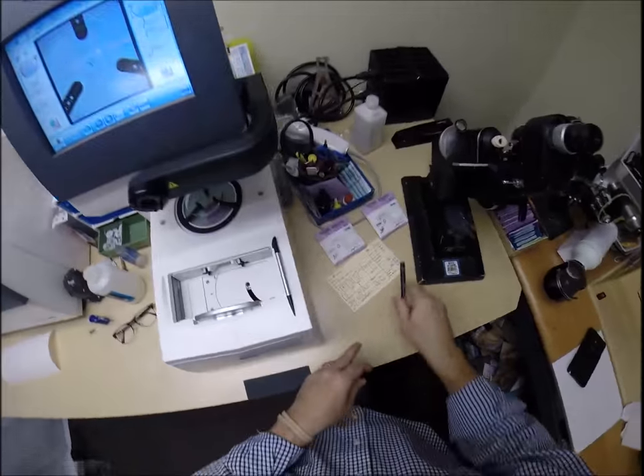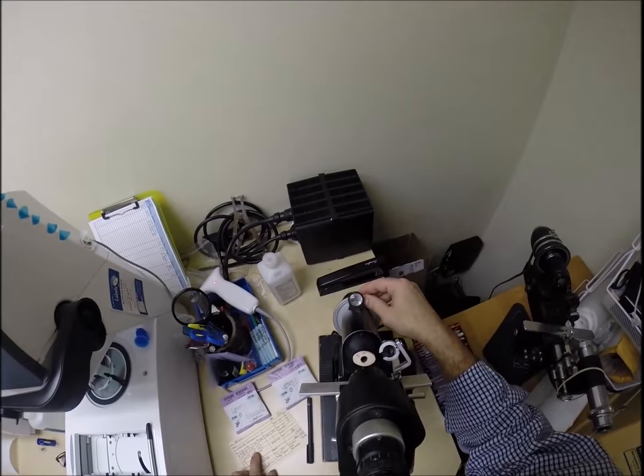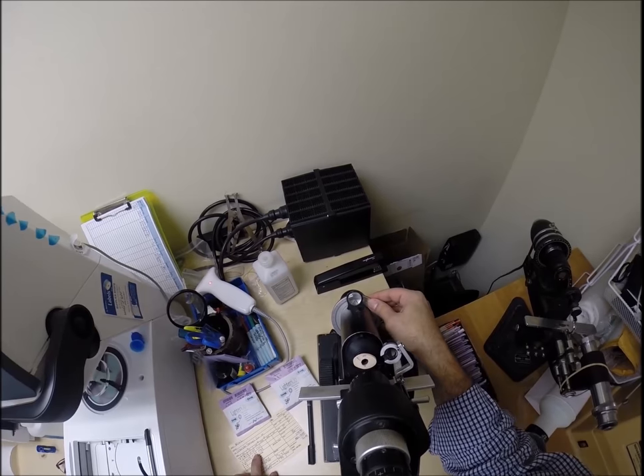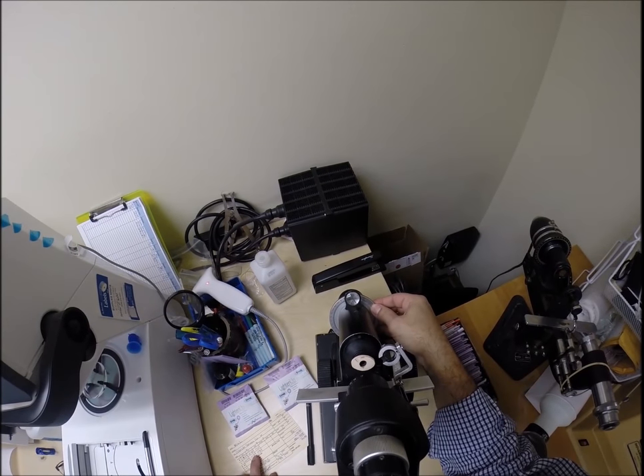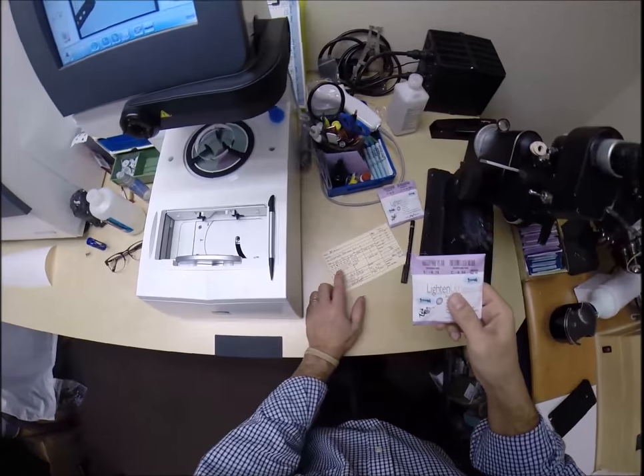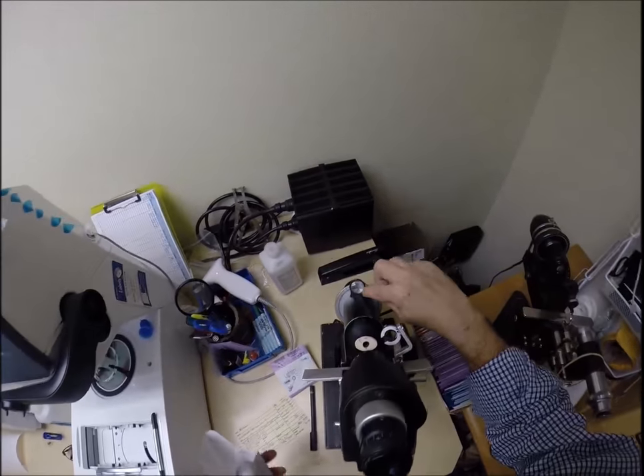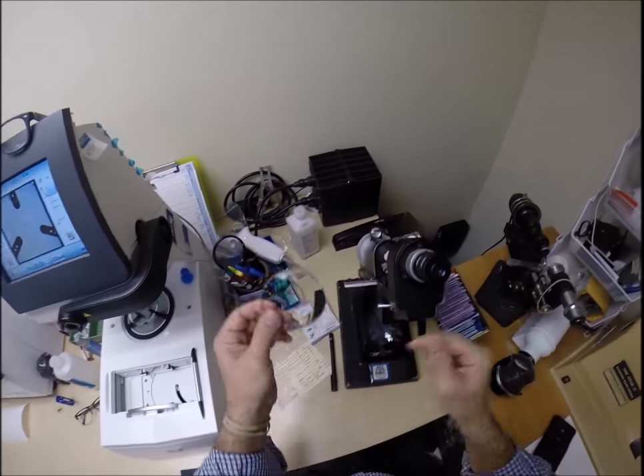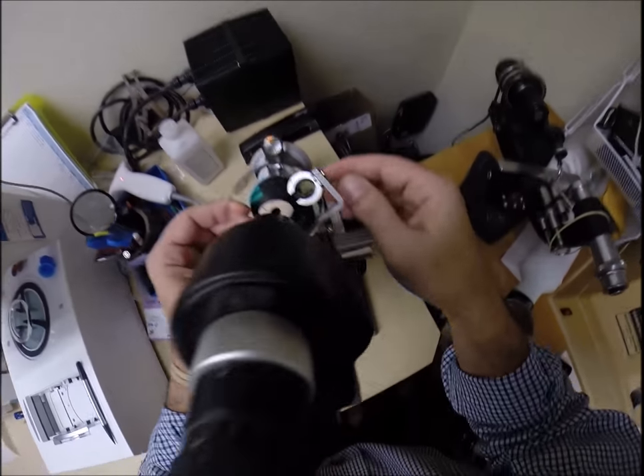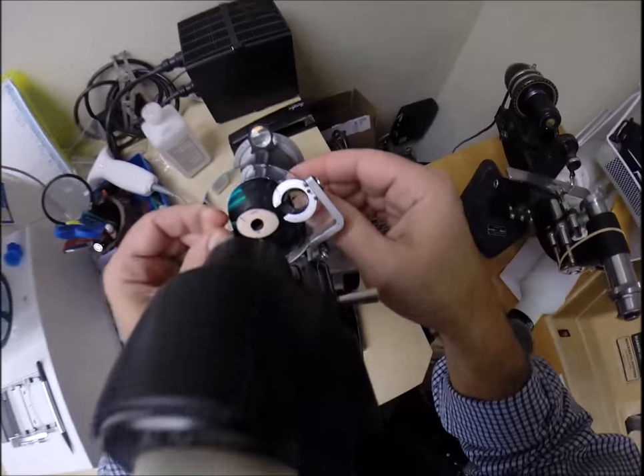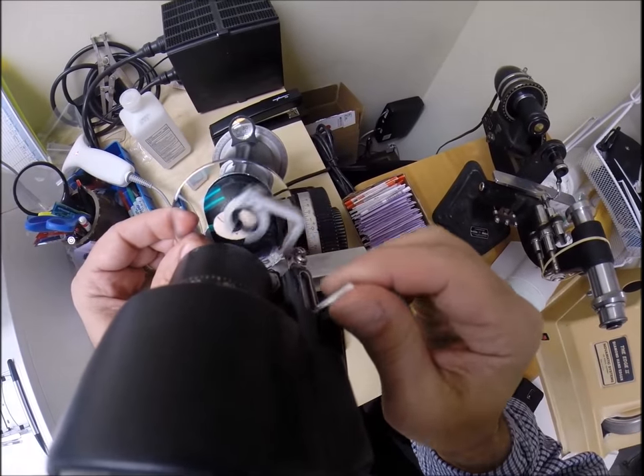Let's do the same thing for the left. Minus 475, minus 50 at 30. Spin the fine-tune knob to 30. And this is minus 475, minus 50 at 30. Take the lens out of the protective sleeve. Put the lens in. Put the power drum on minus 475. Rotate the lens until the sphere power comes in clearly.